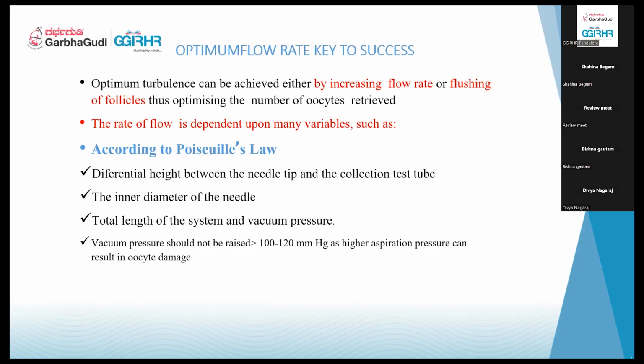For a mature follicle, the pressure that will be used is between 100 to 120 millimeters of mercury. That is optimum. So the ideal gauge of the needle should be 17, and the optimum pressure should be between 100 to 120; ideally, 110 to 120 would be sufficient. What happens if the pressure is more? The cumulus cells present around the follicles might get disrupted, and it might cause disruption of the entire oocyte itself. If it is low, then you might not aspirate the follicle. So having an optimum pressure is very, very important.